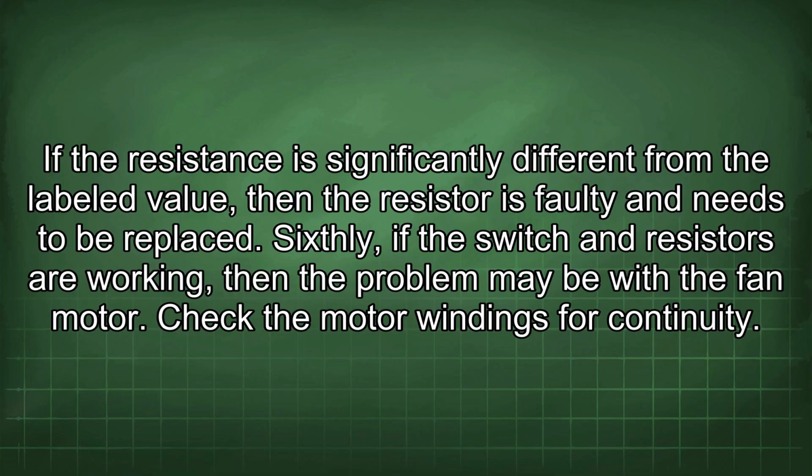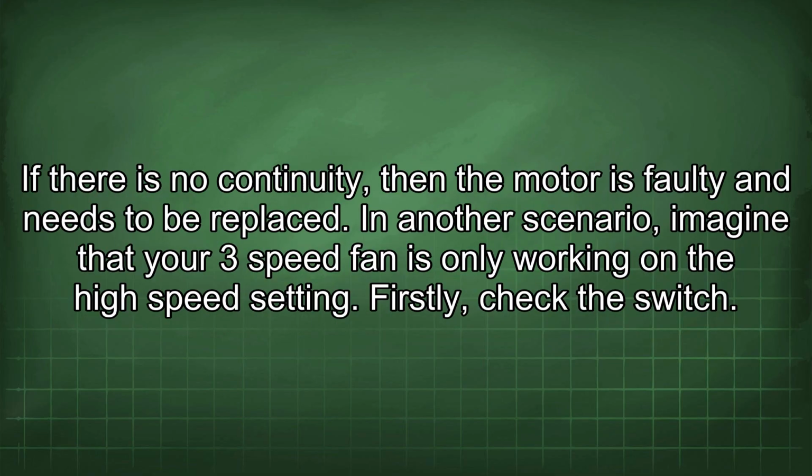Sixthly, if the switch and resistors are working, then the problem may be with the fan motor. Check the motor windings for continuity. If there is no continuity, then the motor is faulty and needs to be replaced.